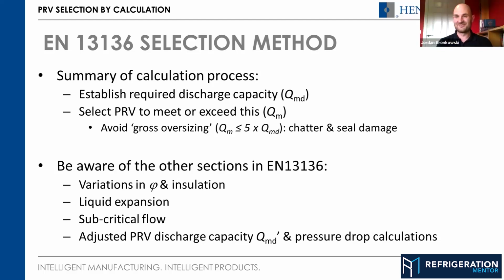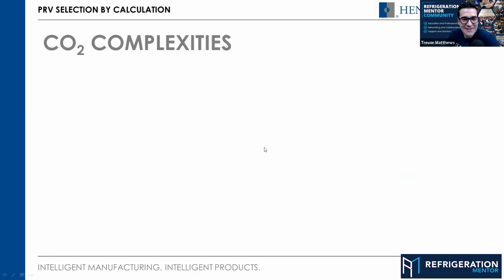So all of a sudden it's blowing out liquid and then it just stops. You know what I mean? That's an issue. Okay, I totally understand that. I don't think I've seen that on a CO2 system. I'll have to dive in a little bit quicker if I ever seen any on the liquid line. I don't think so. They will usually pump back into a vessel or something, and then a vessel would be gas. So I'll have to look into that. Yeah, it's maybe more for conventional refrigerants, as you say. Okay, move on. Anything else on that page you want to pick up on? Let's keep going.